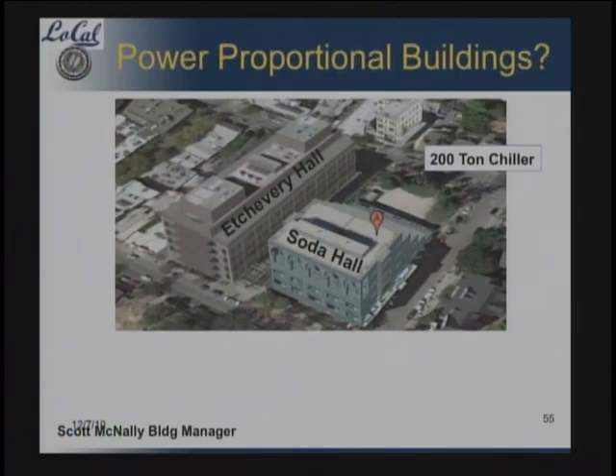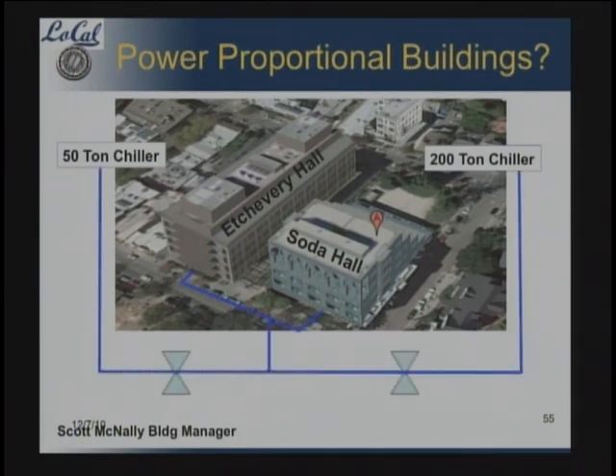...versus, oh, here's one: in Soda Hall we have this 200-ton chiller, and over in Echeverry they have a 50-ton chiller. It turns out this 50-ton chiller would be enough to run both buildings 10 months out of the year, and the other one is more than enough to run them in the 2 hot months. So if all you did was pool the two of those, you'd have something getting much closer to power proportional design.